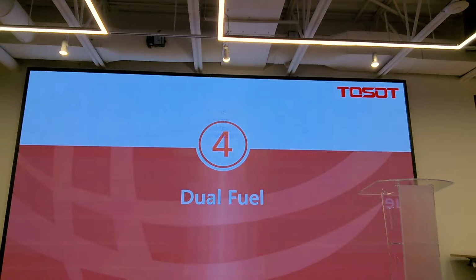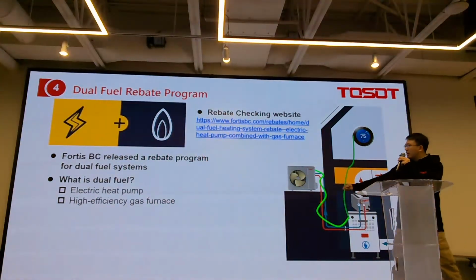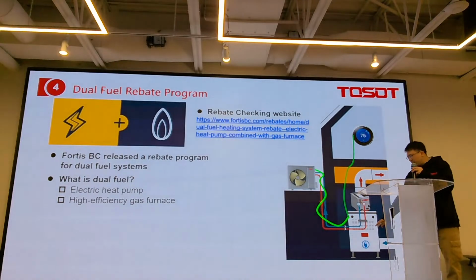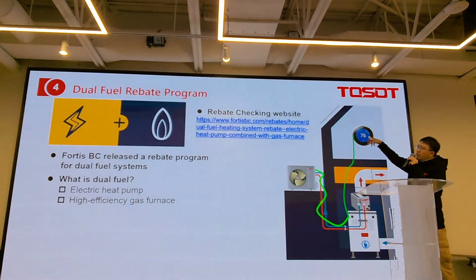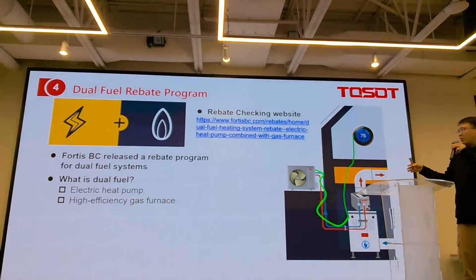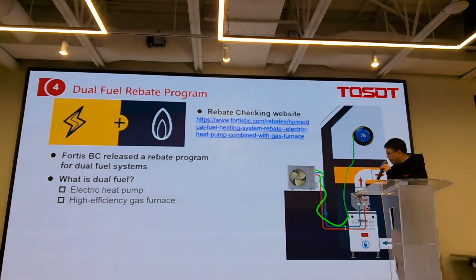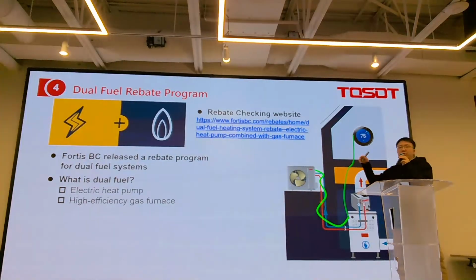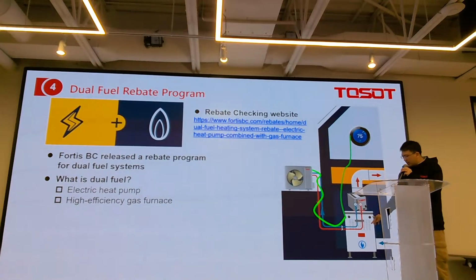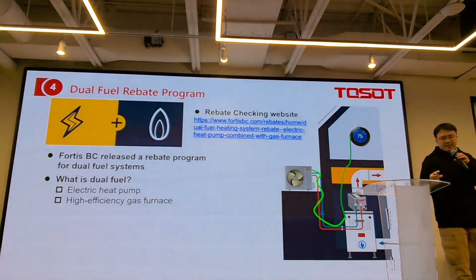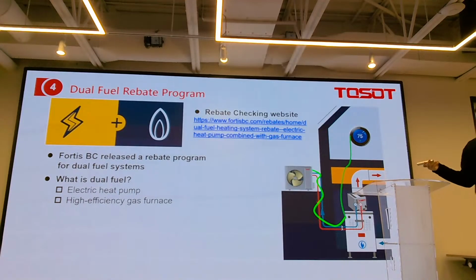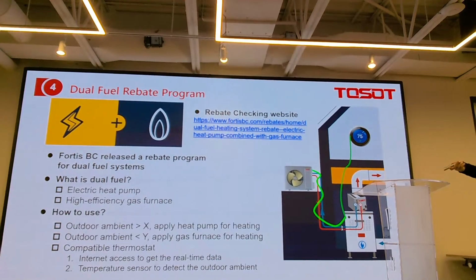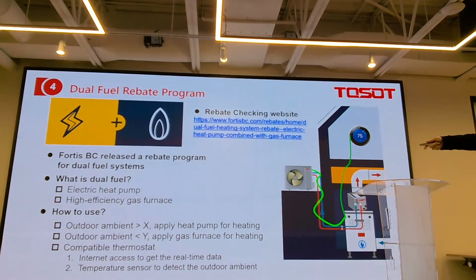And for the dual fuel, it's just the outdoor unit with the A coil together with this furnace. All control is by the thermostat, which means if the thermostat finds it requires the heat pump, then it will turn on the heat pump. But if the outdoor temperature is lower than your setting, then it will turn on this furnace instead of the heat pump. I think it's very common here, right? Does the unit have a balance point, or when it's too cold outside it runs the furnace instead of the heat pump? According to your setting, which means it is all the thermostat.